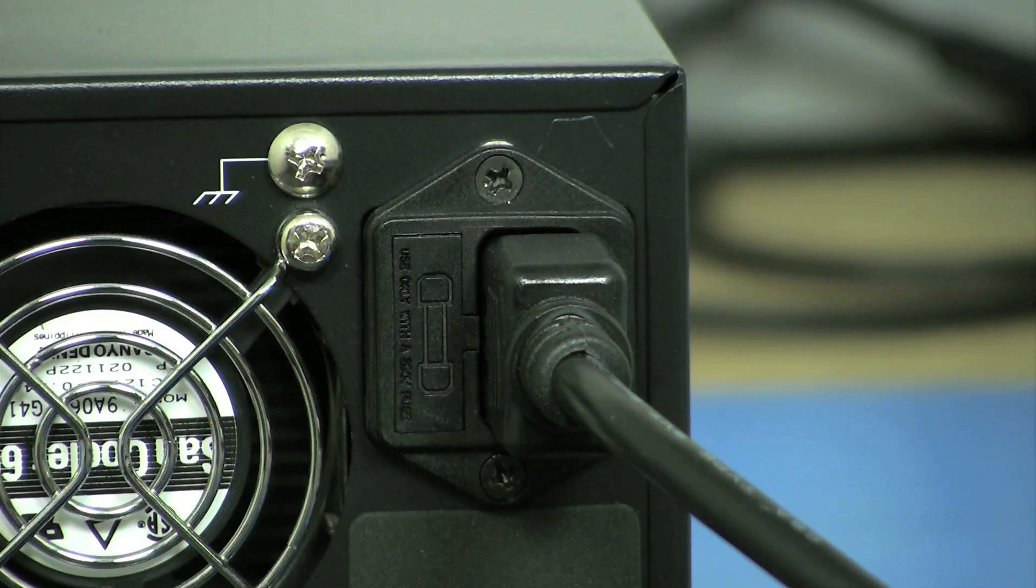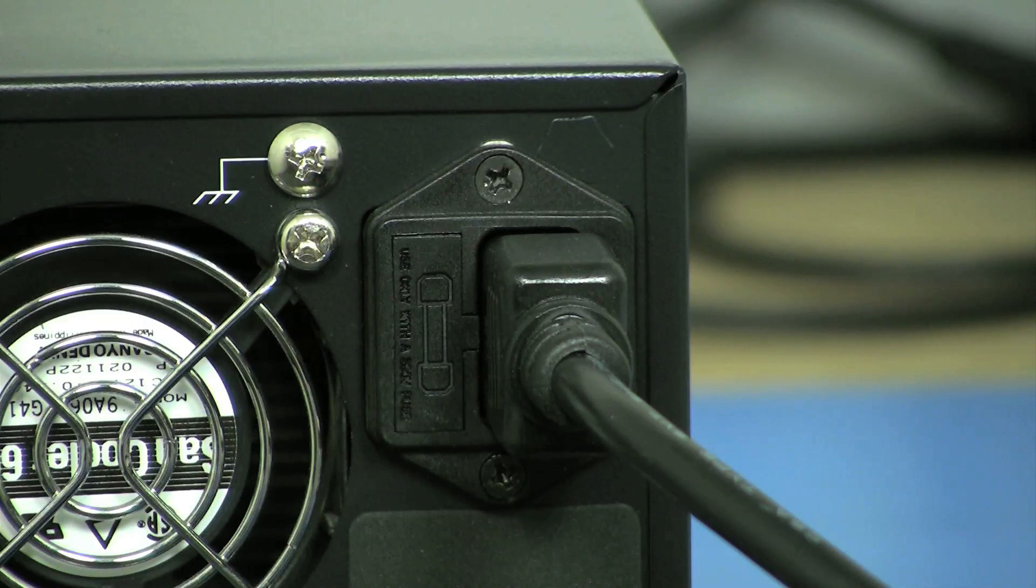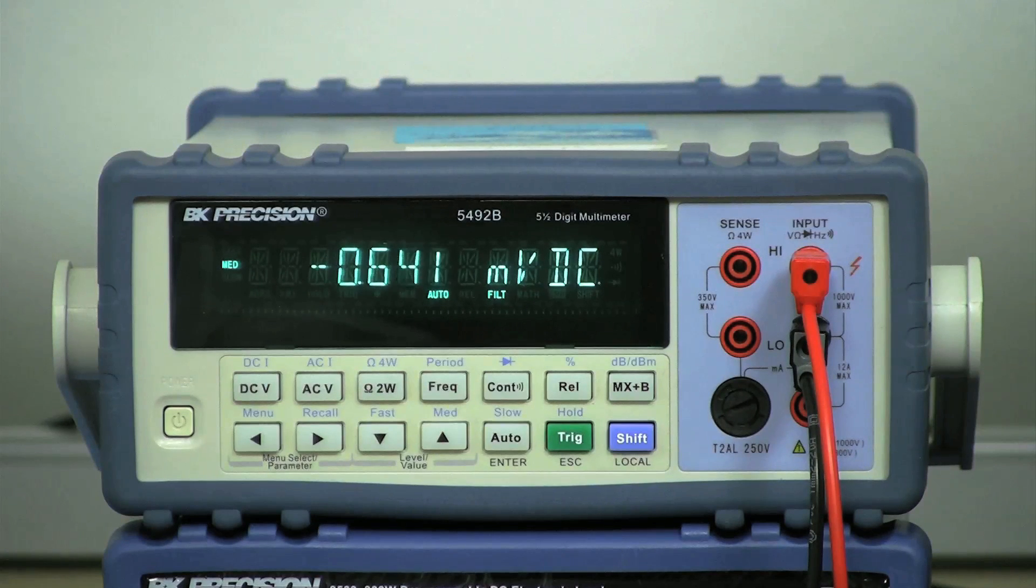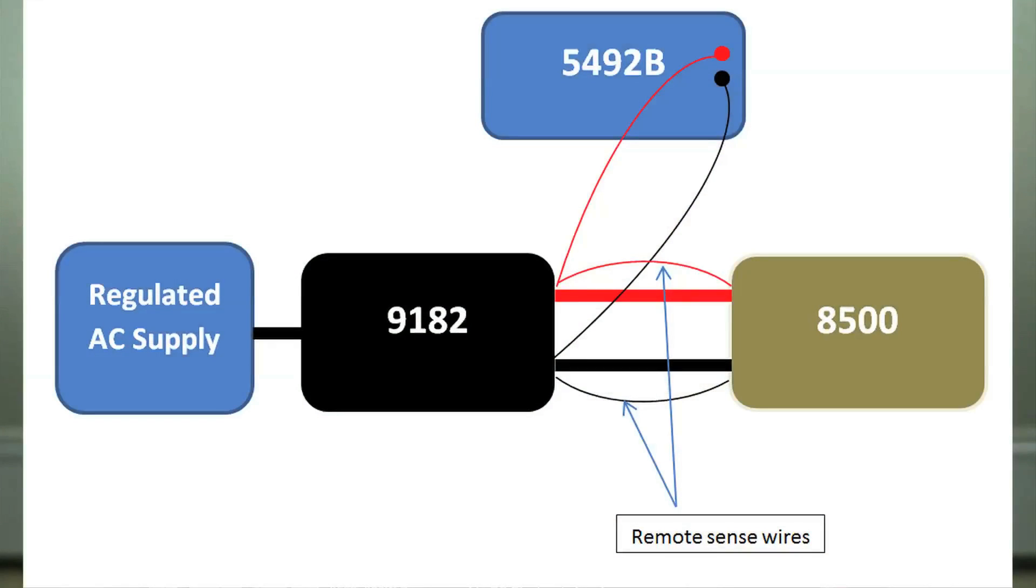A regulated AC power supply will be used to power up the 9182 which will eliminate any load effects caused by fluctuations from the AC input. The 5492B multimeter will be probing the output terminal of the power supply to measure for the voltage change. Here is a diagram of my setup.